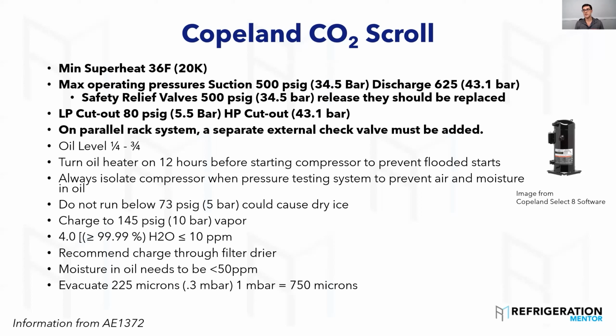This one here, you want to stop any migration. You want to put that in the discharge line. If you're putting a digital on there, it's mandatory to have that external check valve in that discharge line. So make sure you're reading the proper manuals for these compressors. There's so much to learn. Copeland has over 25 different scrolls. They work differently. You need to invest the time to find out which ones you're working with.